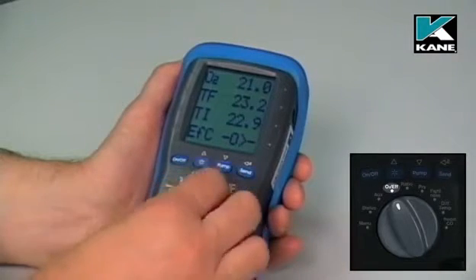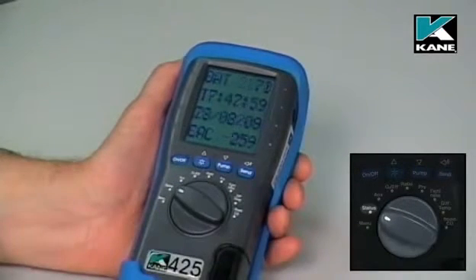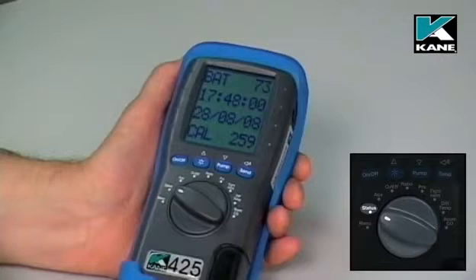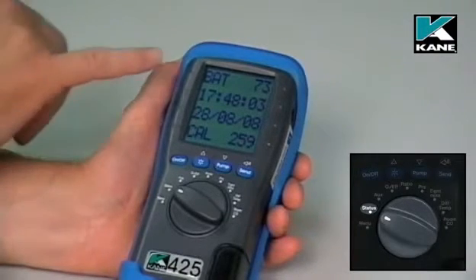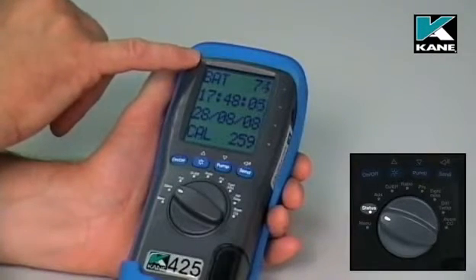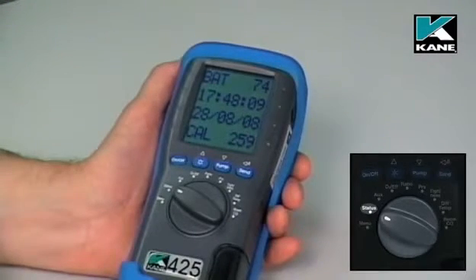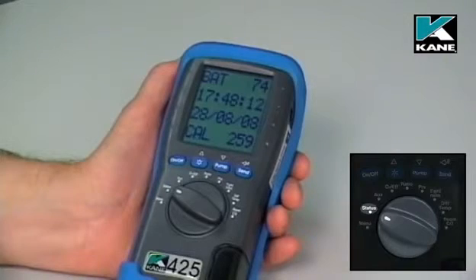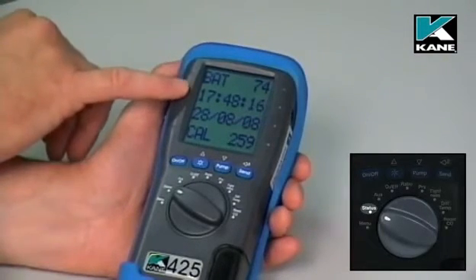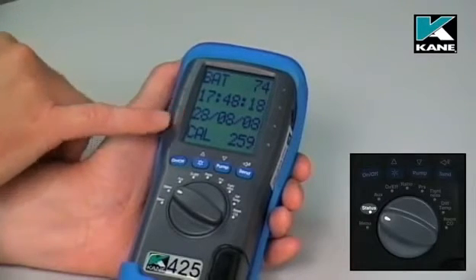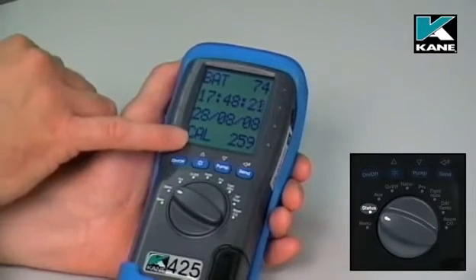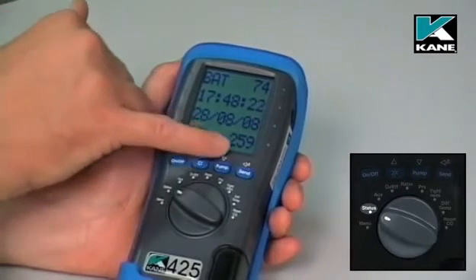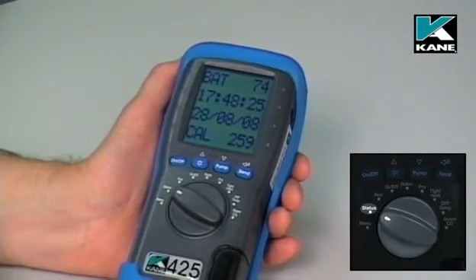Next, move the dial round to the status position. You notice that stops the pump. On the top line, it gives you battery status. If this is lower than 20%, either replace or recharge the batteries. You've got the clock, the calendar, and also on the bottom line, CAL. That's the number of days before the instrument's due for its next check and recalibration.